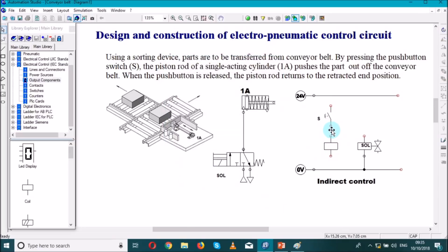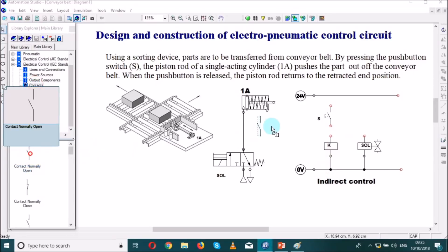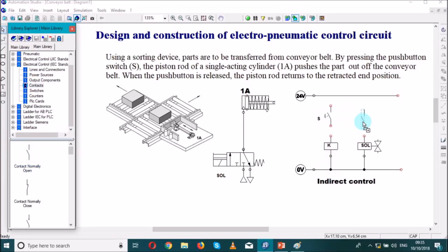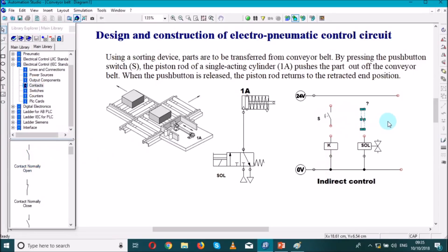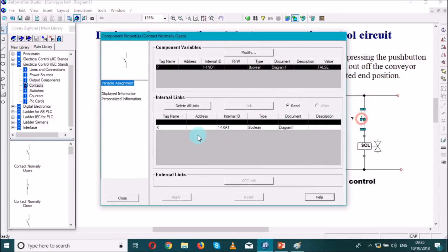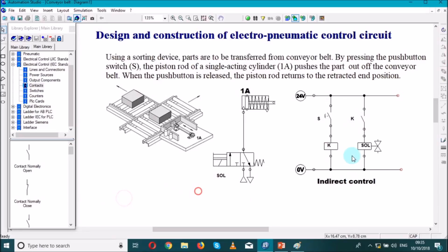And then as we need to control the solenoid by using K, we go to contact and we search for a normally open contact which will be closing by supplying the contactor. So we link the contactor here and the solenoid. Let us link this contactor to the contactor like that one. We link and then we close. Now we have an indirect control circuit.